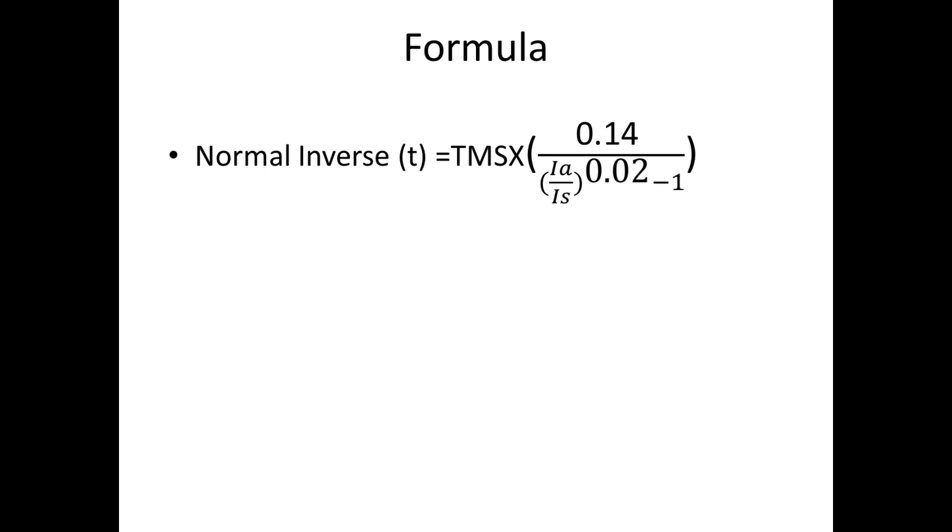For very inverse we get: TMS times 13.5 divided by (Ia/Is) to the power 1 minus 1.